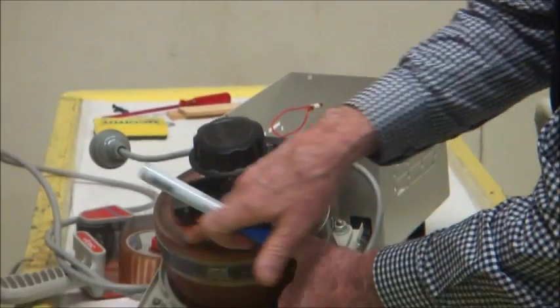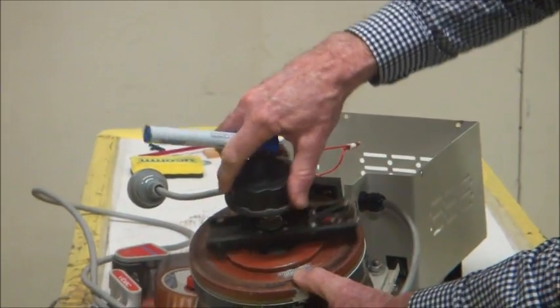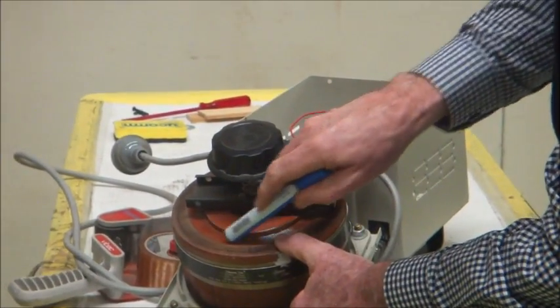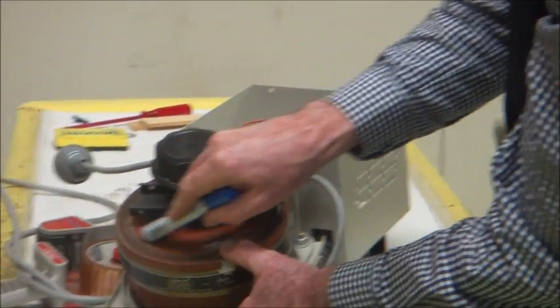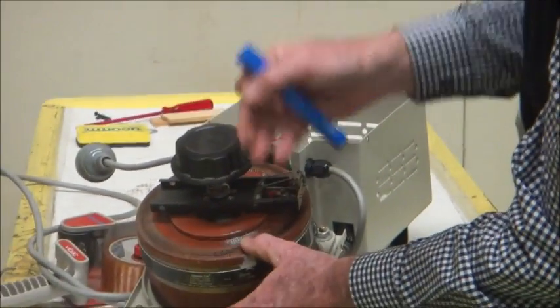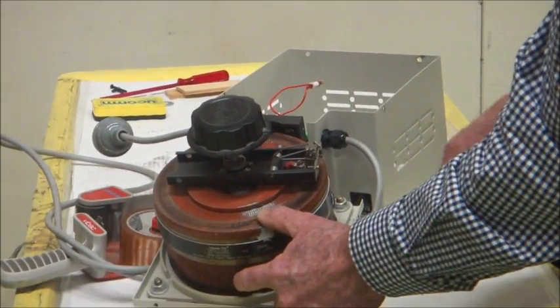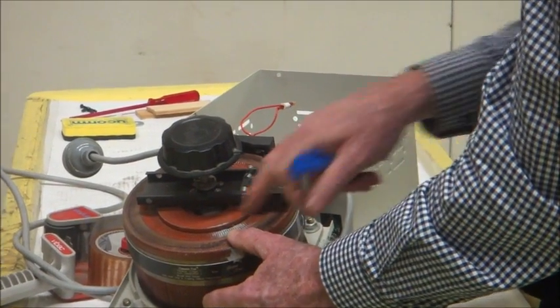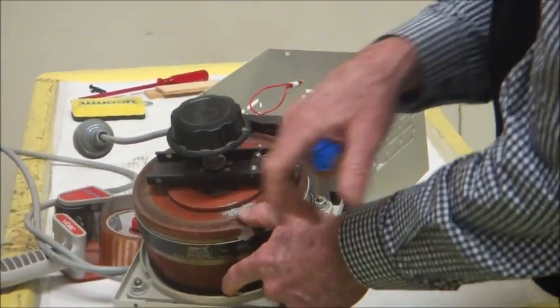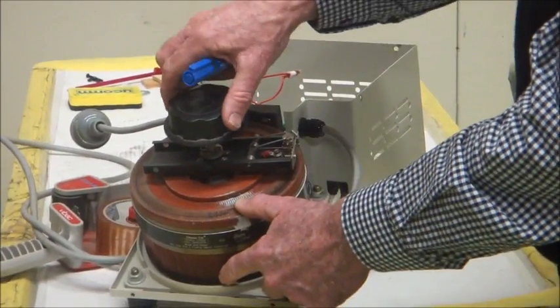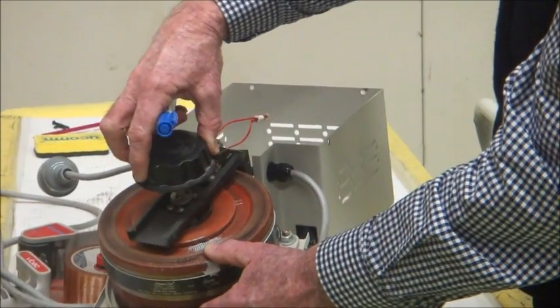Because this is actually acid etched and machined so that you get a smooth movement of the brush. The windings here are all epoxy encapsulated, so they're epoxy to hold the winding solid. Normally you have to use also 180 degree C enamel wire to make sure that it is capable of high temperature.